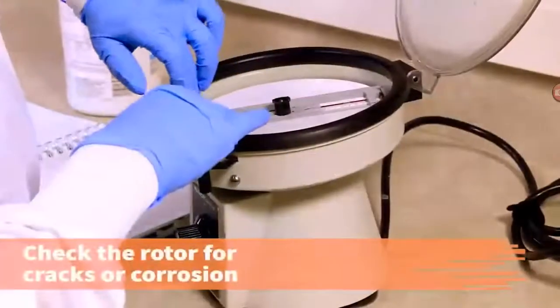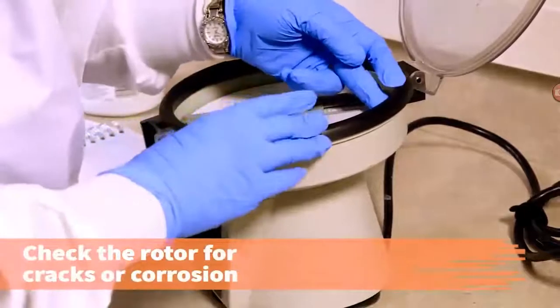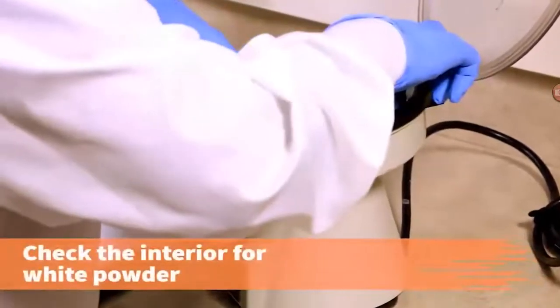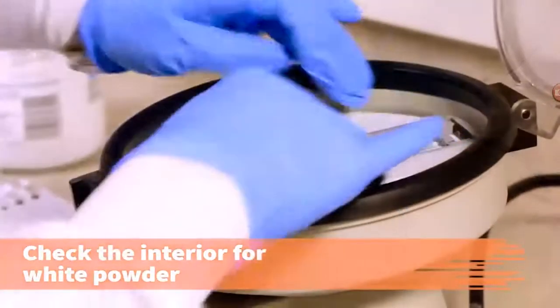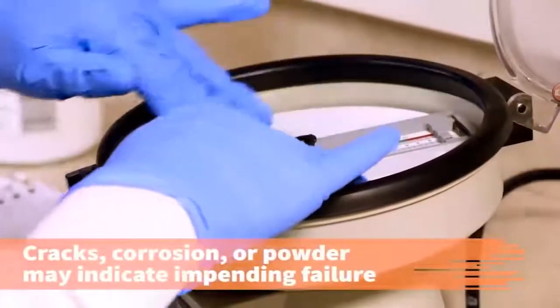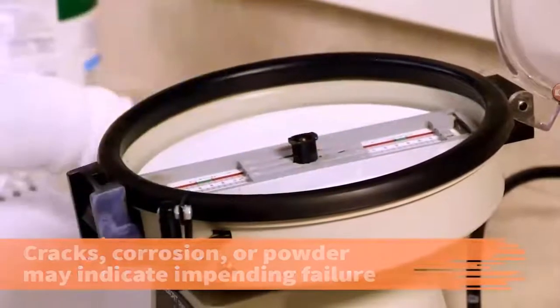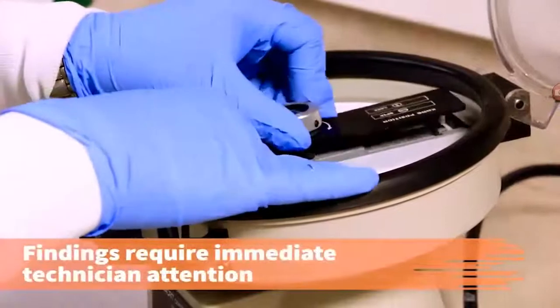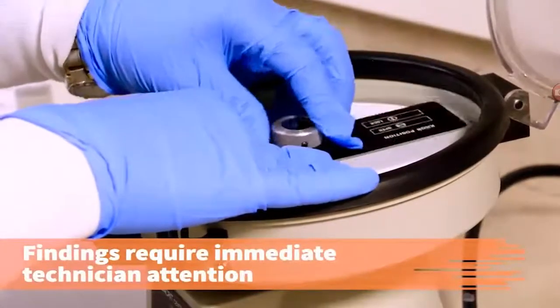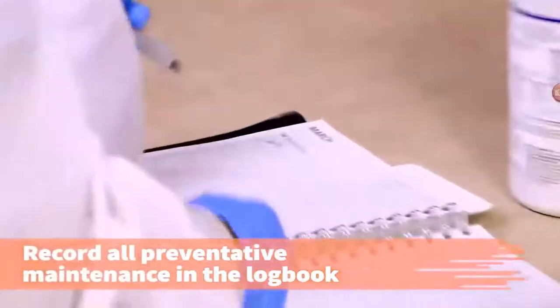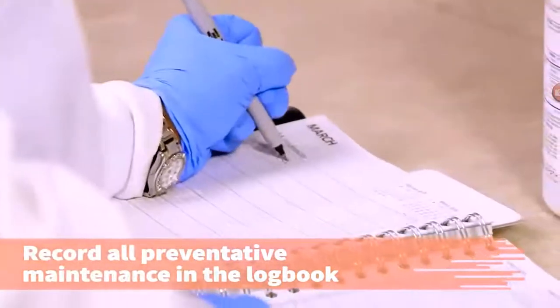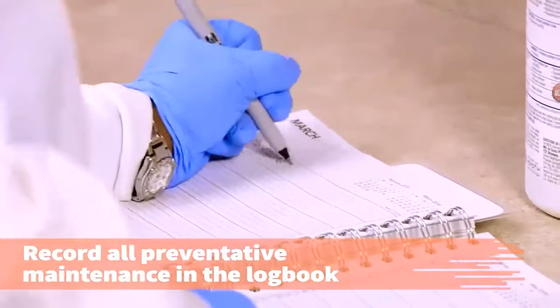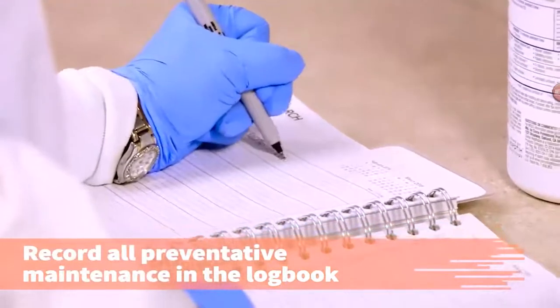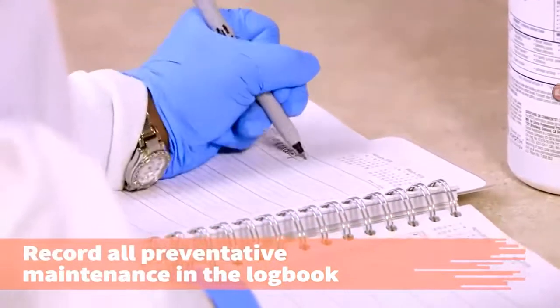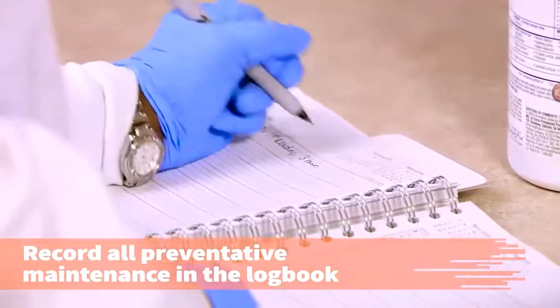Check the rotor for cracks or corrosion and check the interior for signs of white powder. Cracks, corrosion, or powder may indicate impending rotor failure. These findings require the immediate attention of a service technician. Record all preventive maintenance in the laboratory logbook. Recording maintenance is necessary to maintain warranties and to comply with regulations established by CLIA and other regulatory agencies.